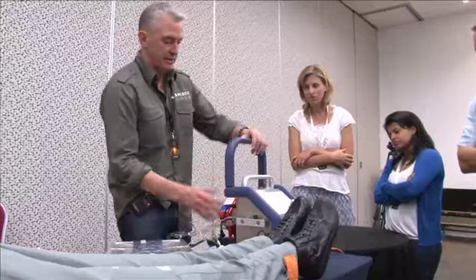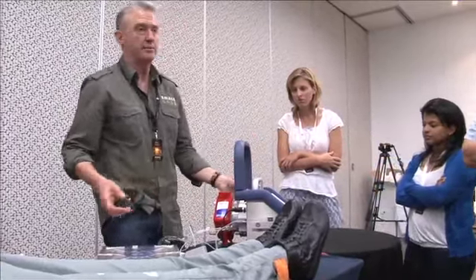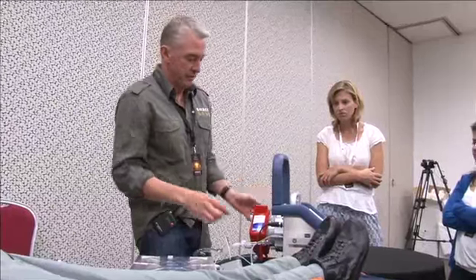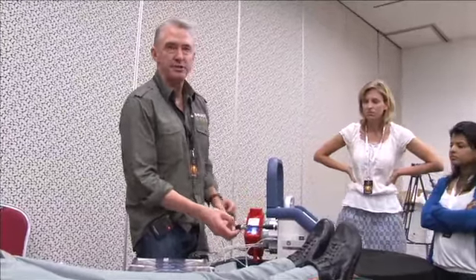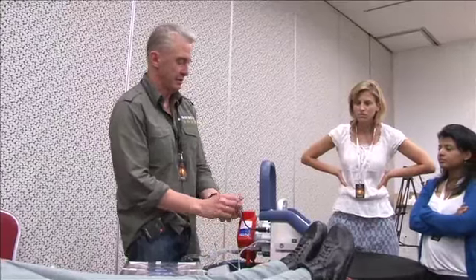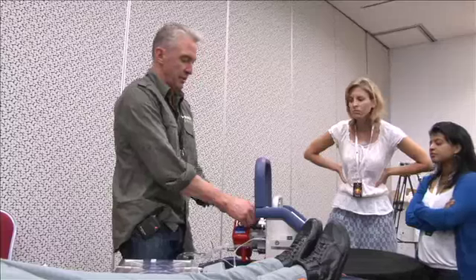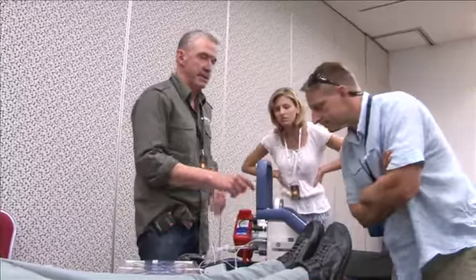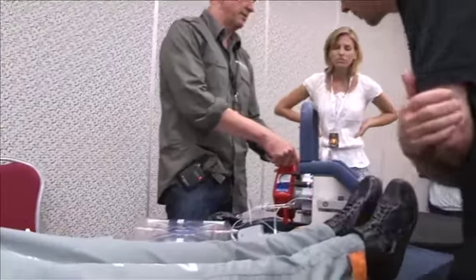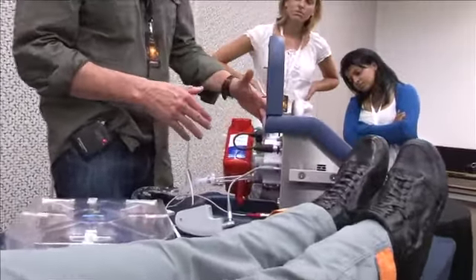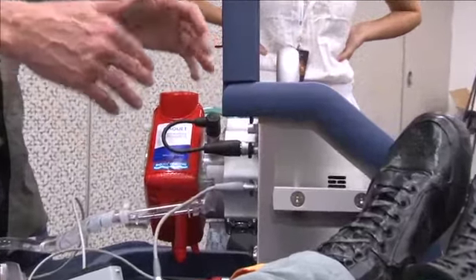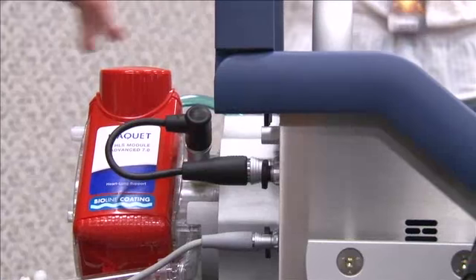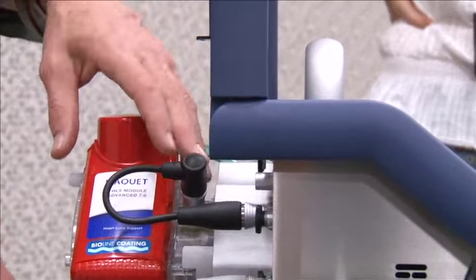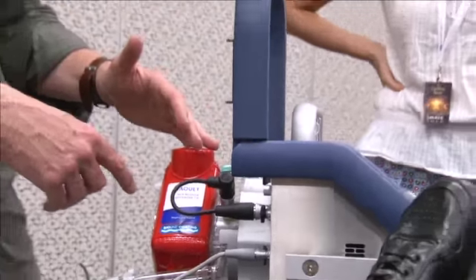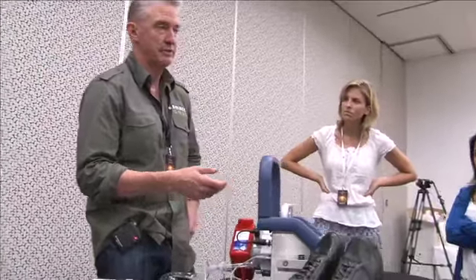Now there are a few other things that this pump does that make it very, very user-friendly. The first is that it has some internal pressure sensing. This is a little pressure transducer here that plugs into the pump over here. And what this pressure does is measure the pressure between the pump and the oxygenator. That's called the pre-membrane pressure, and that's the highest pressure part of the circuit.